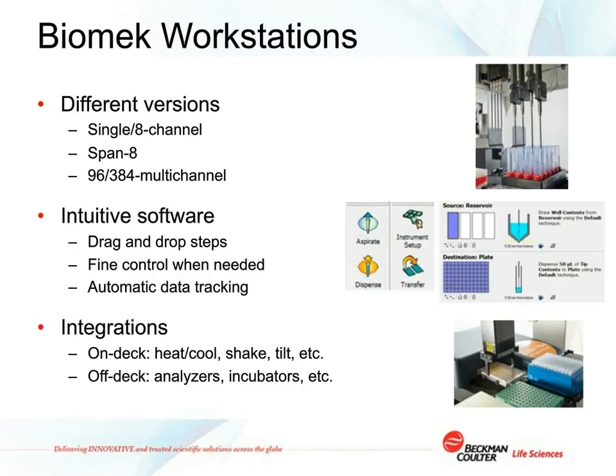The Biomek systems are designed to be flexible, including the ability to integrate different devices. On-deck integrations can include heating or cooling positions, plate shakers, or plate tilters. Off-deck integrations for additional instruments can sit next to the instrument or be connected through conveyors — including analyzers, incubators, or plate storage — increasing either the complexity of workflows or the percentage of a workflow that is automated.